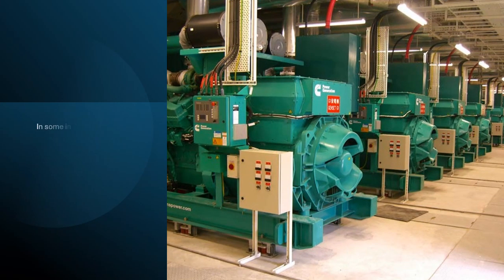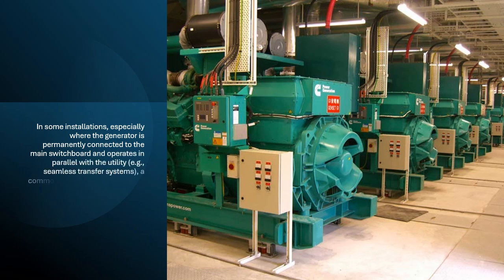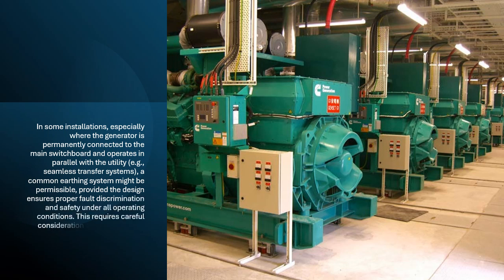clearance. In some installations, especially where the generator is permanently connected to the main switchboard and operates in parallel with the utility, e.g., seamless transfer systems, a common earthing system might be permissible, provided the design ensures proper fault discrimination and safety under all operating conditions. This requires careful consideration and adherence to specific standards.